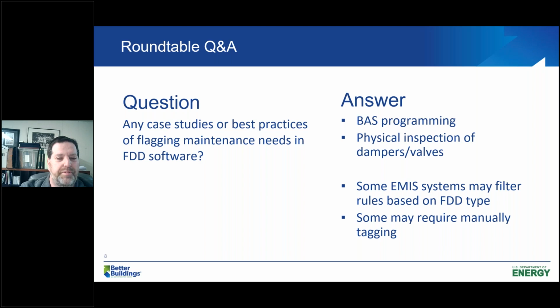With physical issues, some EMIS systems may filter rules based on an FDD type. Is it O&M? If it requires replacement of a part, like an actuator or filter that needs to be replaced, it should help identify that specific measure so you can give that as a work order to your O&M group. And then there are changes for sequence of operation, which is another one to find.